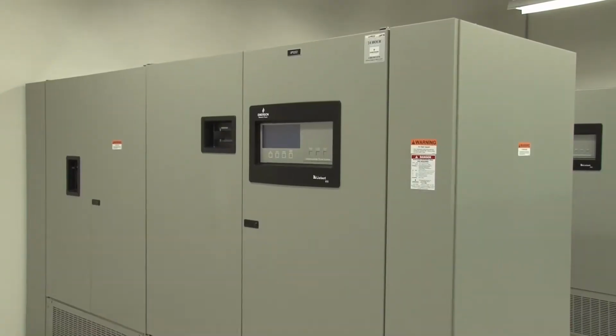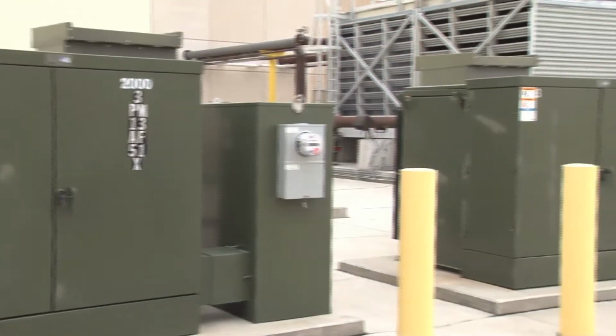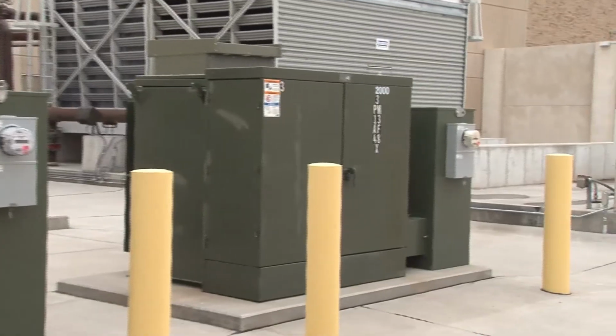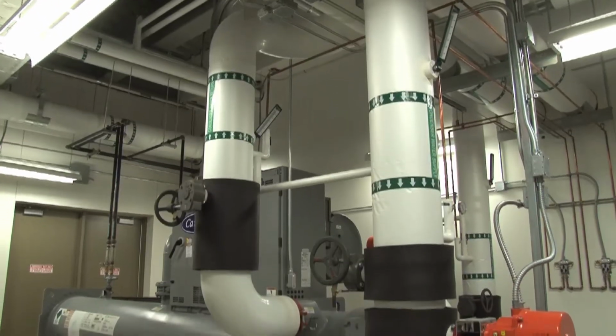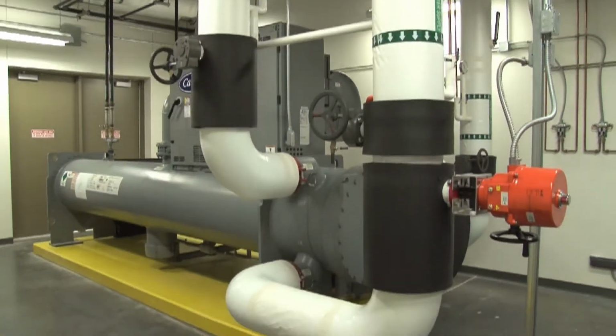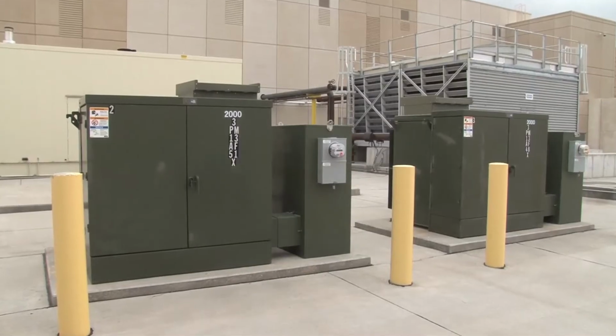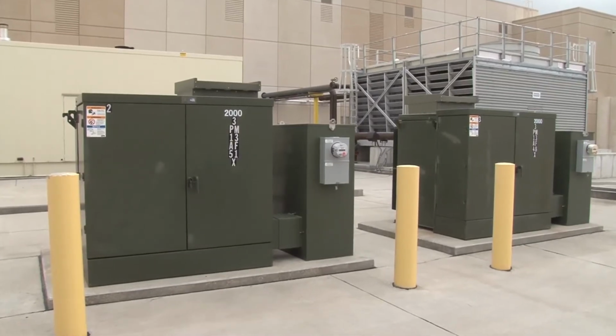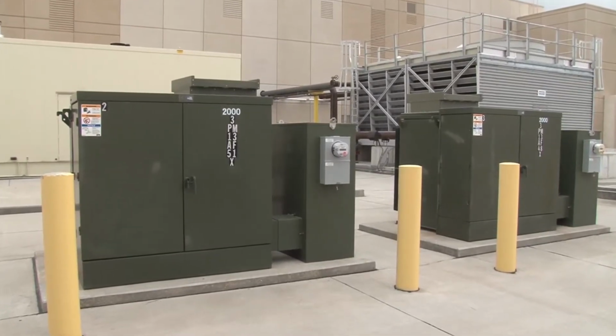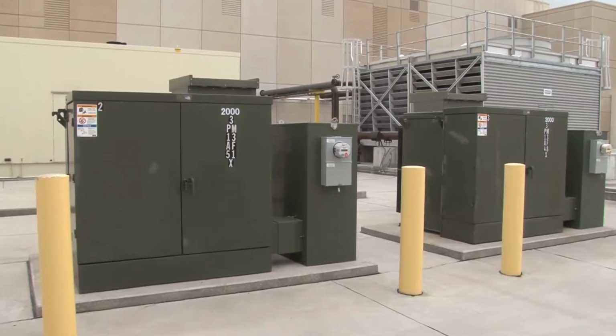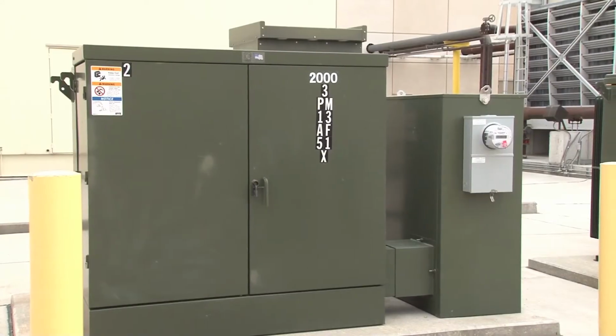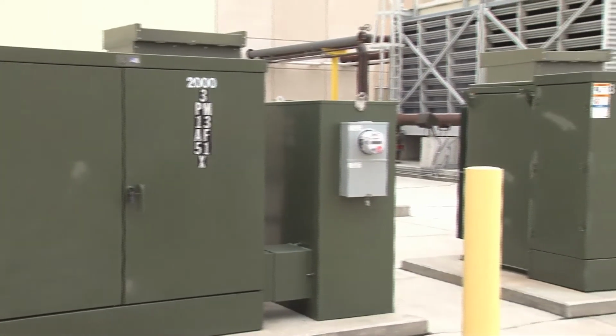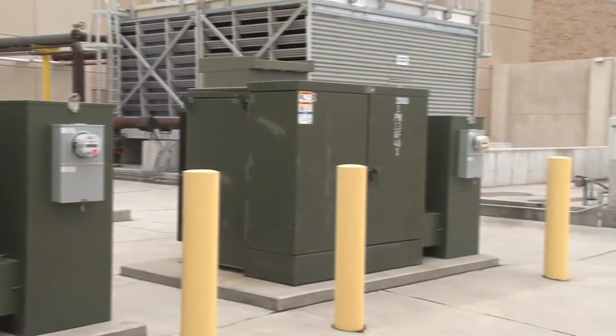Tier 4 is based on the redundancy. Redundant UPSs, redundant power from utility, direct lines from separate utility substations, redundancy in your cooling, redundant chillers, redundant chiller paths, redundant electrical paths. So really the key word is redundancy. We have 2 direct lines from separate substations. Each is 13,800 volts with 12 megawatts. Then it goes to step-down transformers where we bring 2 4,000 amp 480 volt services into the building.